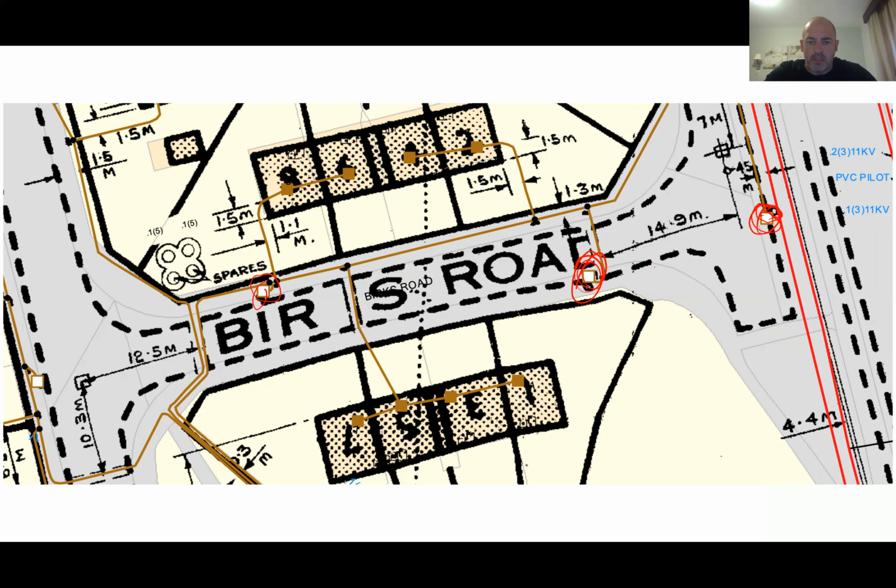In terms of locating, what this also means, I've worked in this street quite a lot, and what you can actually do in this street, by applying your genny signal here and here, you can actually locate all that network. So I call that easy street. Nice and easy, just by using the columns, we can locate all that network. Okay, so that's one example of a TEED system and where the lighting is shown on the plan.